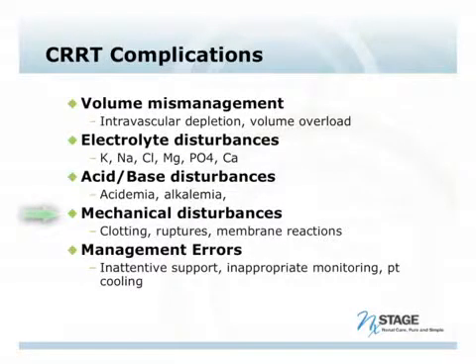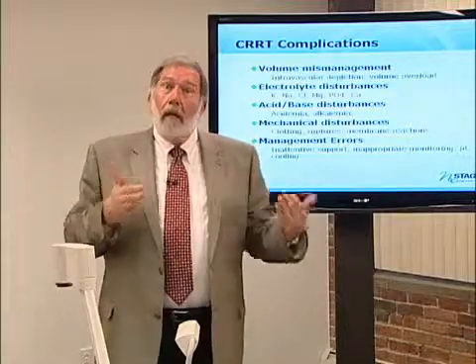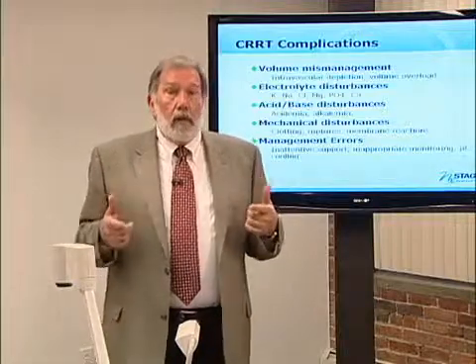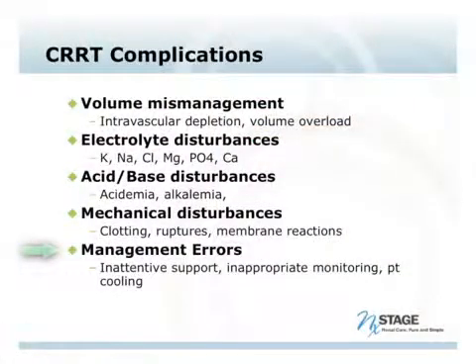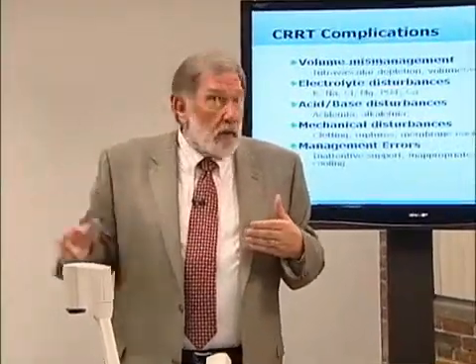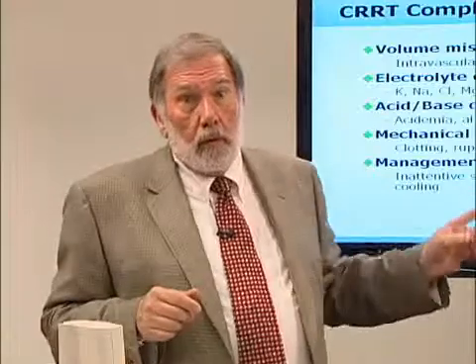Then we move into mechanical issues such as clotting, membrane rupture — seen in both intermittent and continuous therapy — and membrane reactions. If a patient is not biocompatible with the membrane being used, that's an important issue that should come to the top. Finally, and perhaps one of the more important complications in CRRT, is management errors: not being attentive to what's going on, allowing alarms to go unaddressed, or pushing a button to clear an alarm without looking at the root cause. Also, understanding that you are cooling the patient — so a patient may be developing a febrile response but you're masking it with cooler dialysate.